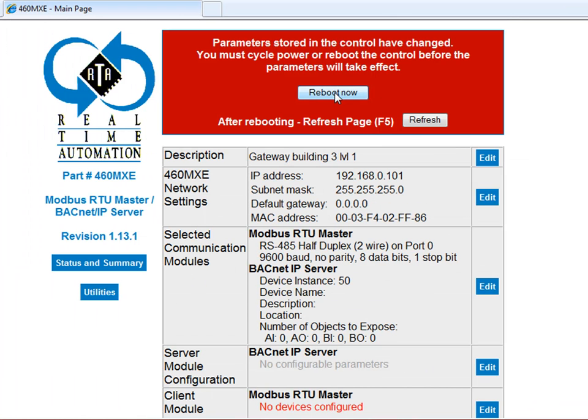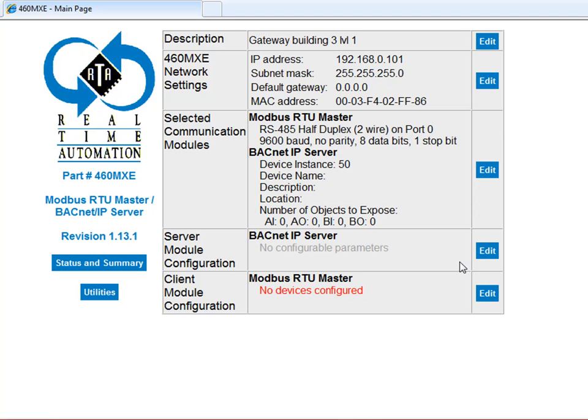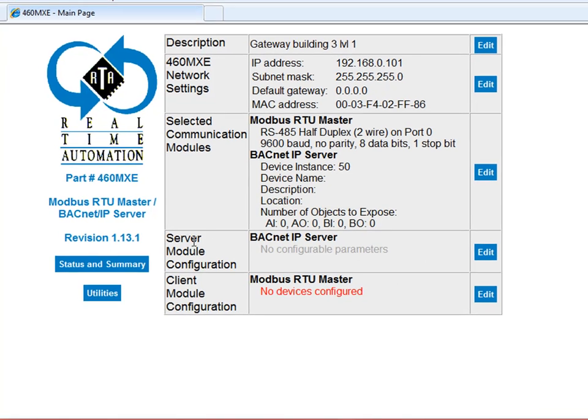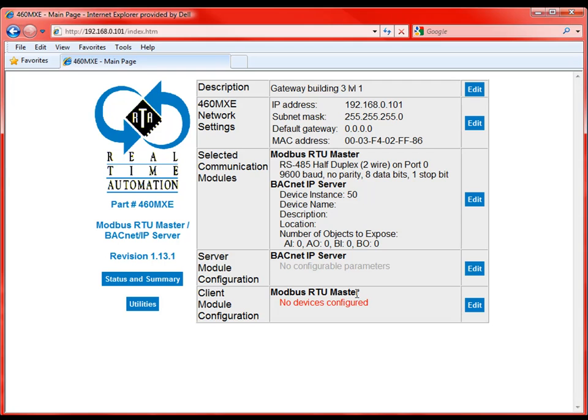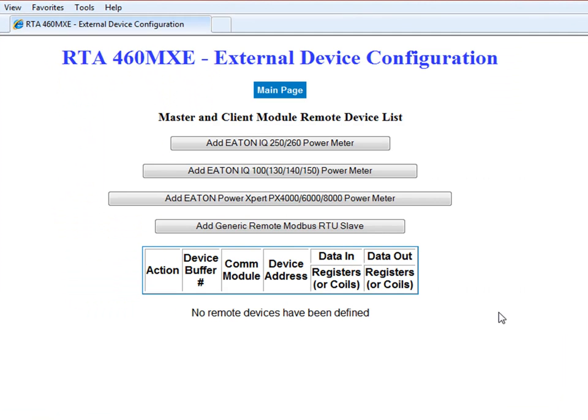Because we did make a change, if you go reboot now, and then a quick refresh, the unit will restart. Now if we'll go to the server module configuration, the BACnet IP server, there's nothing else to do there. It's defined that we are device instance 50, and there's really nothing else to do. It's just presenting the data to the BACnet IP client. What we need to do our work is in our client module configuration, and that is configuring our Modbus RTU master. We're going to have to add the slaves that it's going to pull. And those slaves are, of course, the power meters out on the network that we're looking to grab data from.